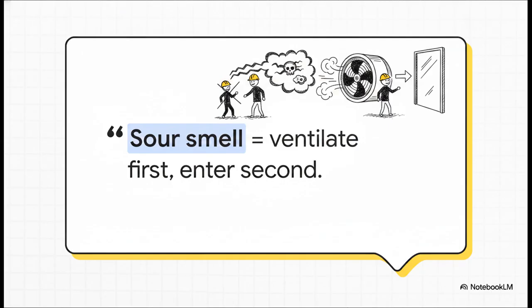That sour smell, that's not the SF6 gas itself. Pure SF6 is completely odorless. That smell is a dangerous decomposition byproduct. It's created when the incredibly hot electrical arc physically burns and breaks down the SF6 gas during a fault. It signals a totally hazardous environment, meaning you have to thoroughly air out that compartment before you or anyone else breathes it in or does any work inside. Safety always, always comes first here.